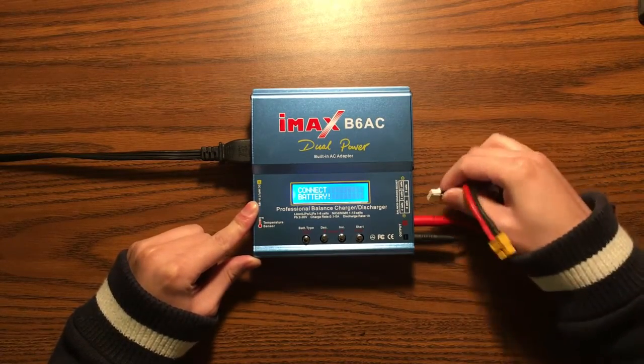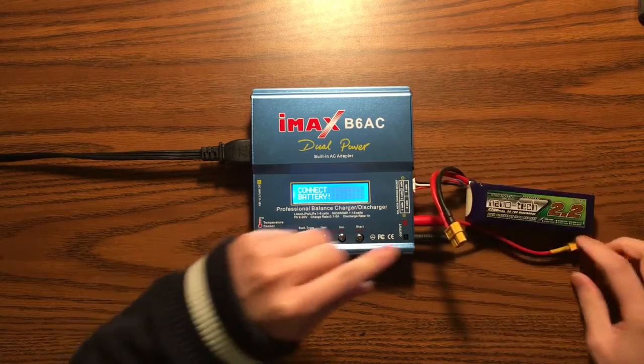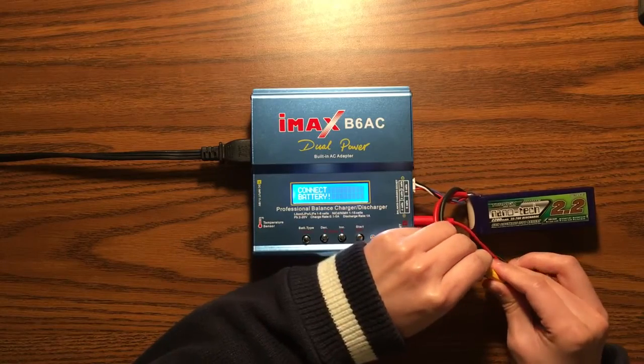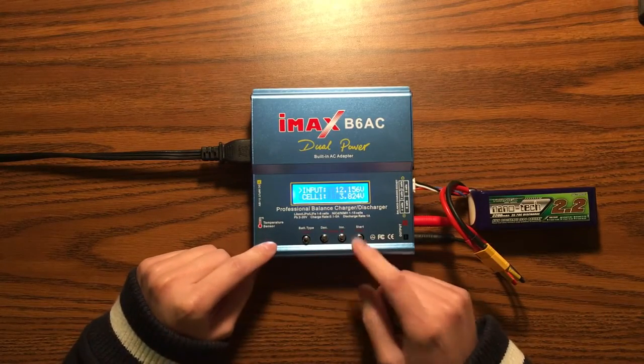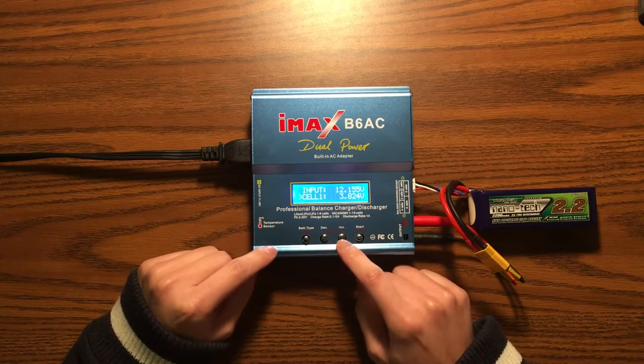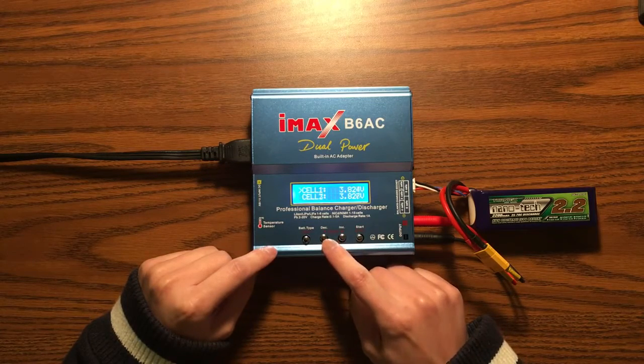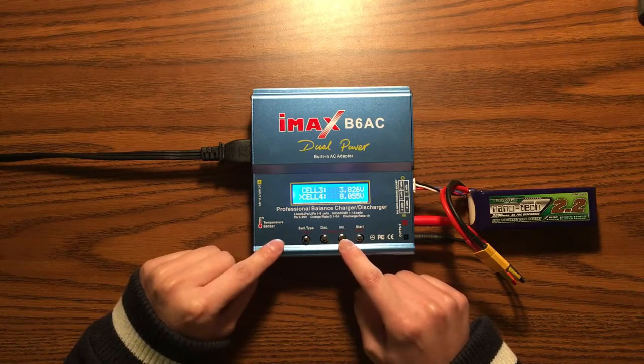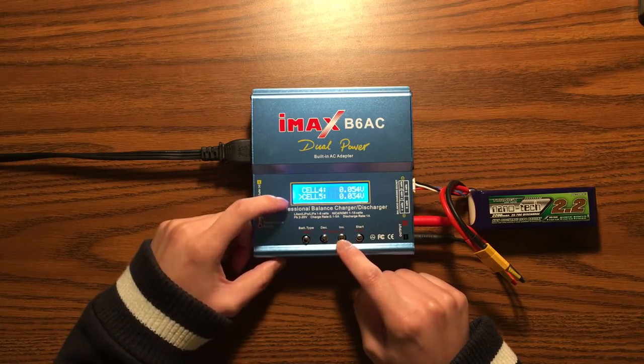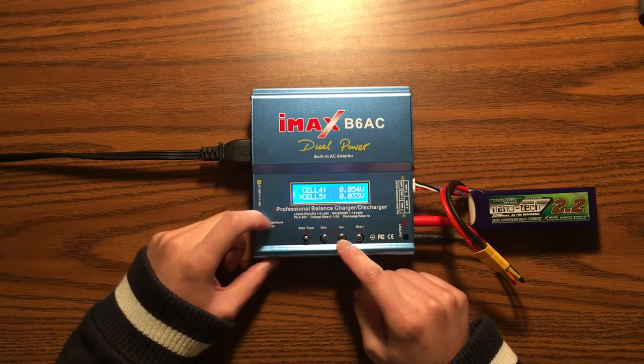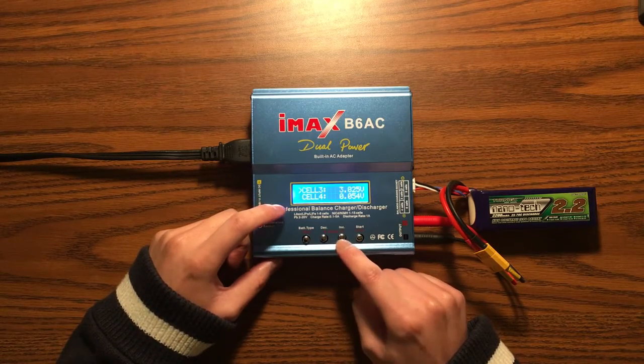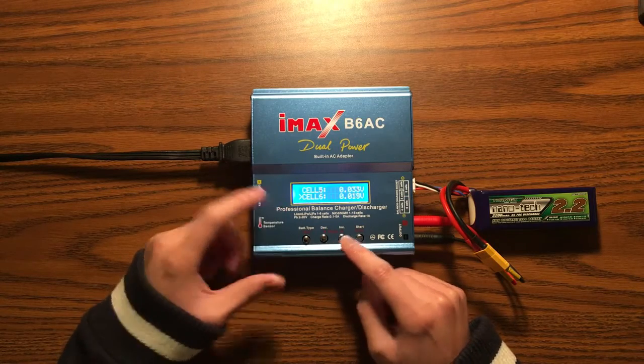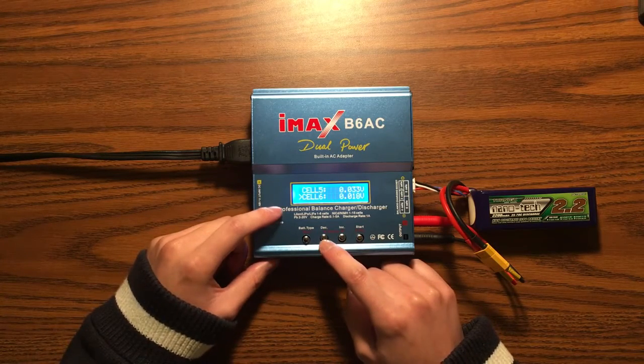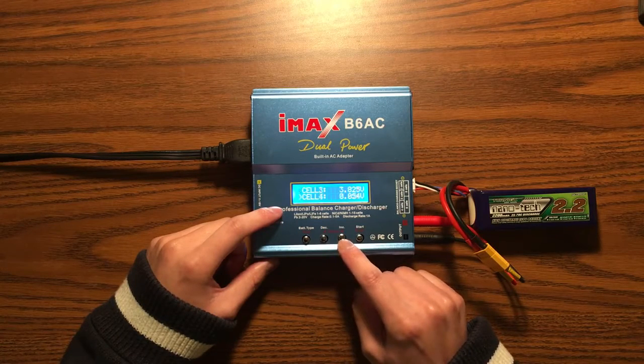Even with a 3-cell battery, you can still do the calibration, and it works. The only problem is you can only calibrate the first 3 channels, not the last 3. So you can calibrate 1, 2, and 3, but not 4, 5, and 6, because they're not connected.